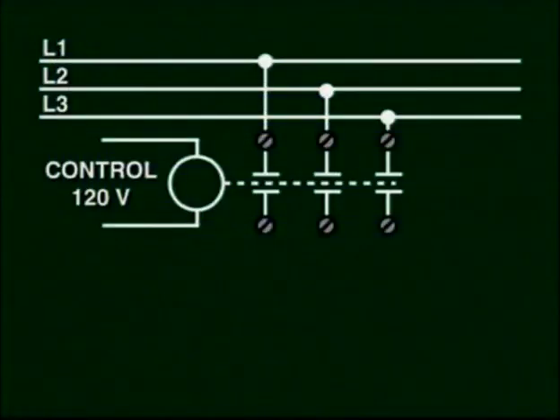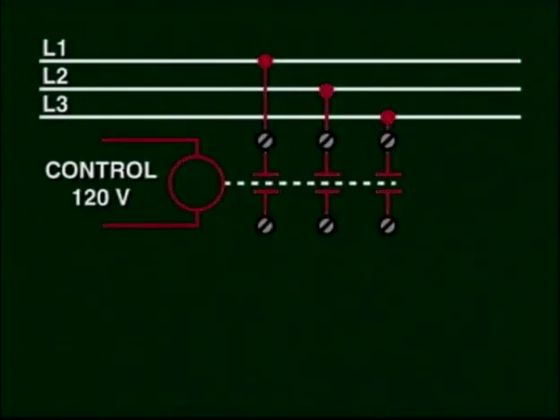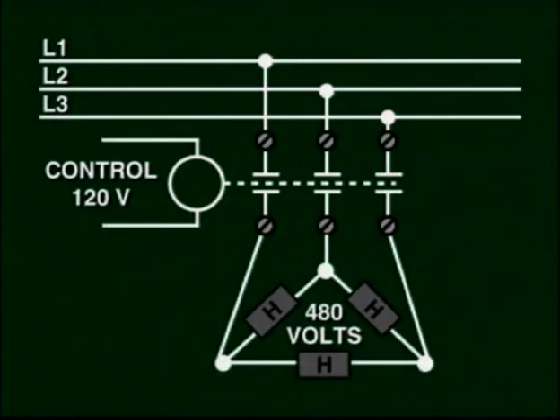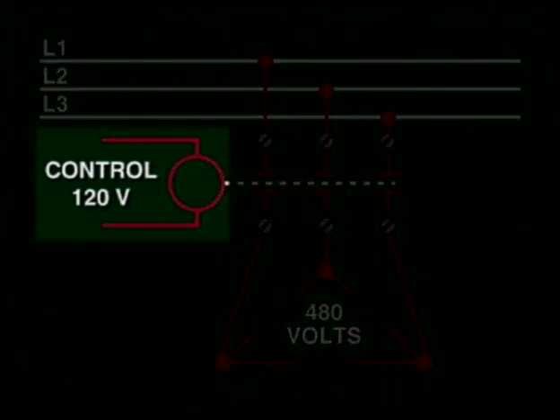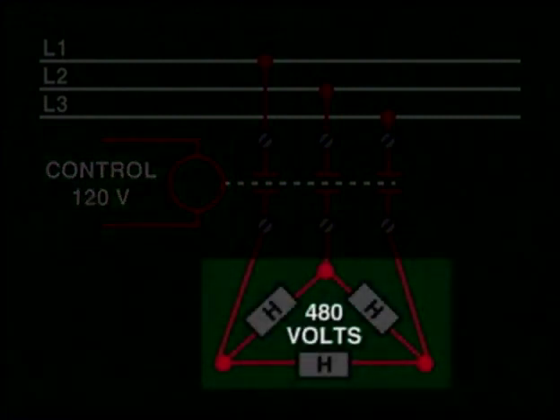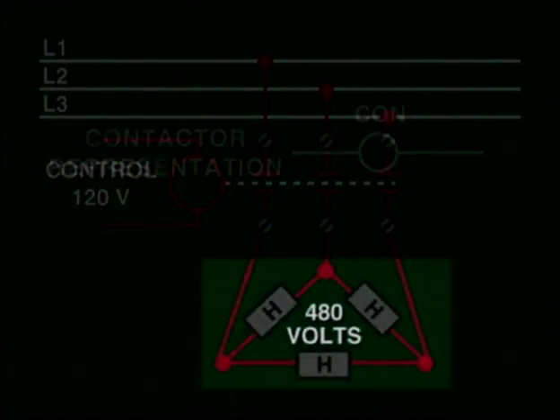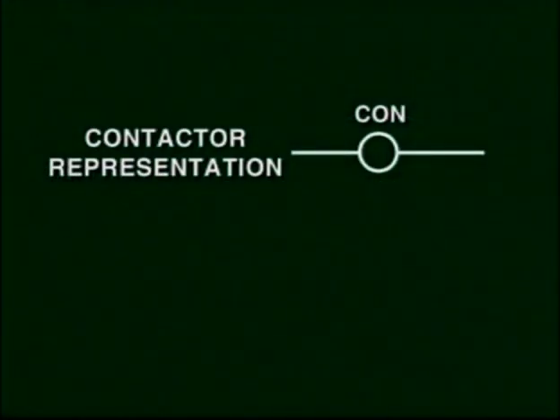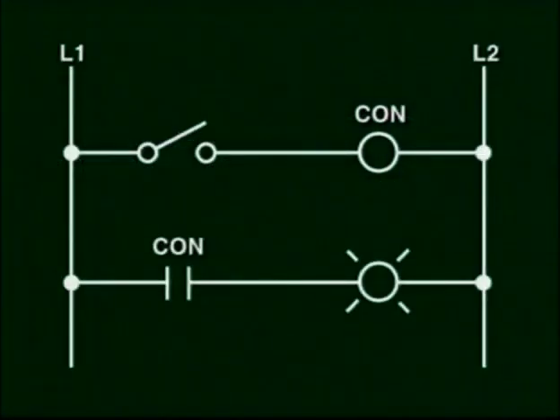The coil in the contactor indirectly controls the operation of its load. That is, when the coil is turned on, its high-power contacts close, therefore providing power to its load. For example, this three-phase, three-pole contactor connected to a three-phase heater will give power to the heating elements once there is control power to the coil. This control power may be 120 volts AC, while the power provided to the heaters through the power contacts could be 480 volts. Contactors are represented in ladder diagrams with this symbol, very similar to a relay.